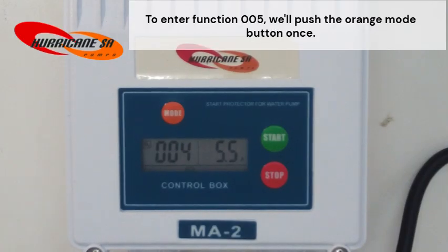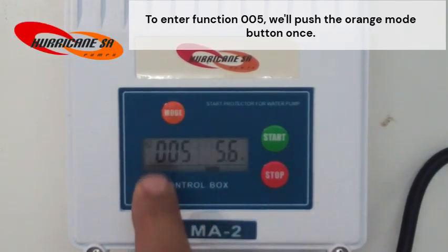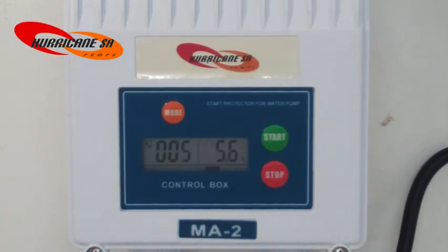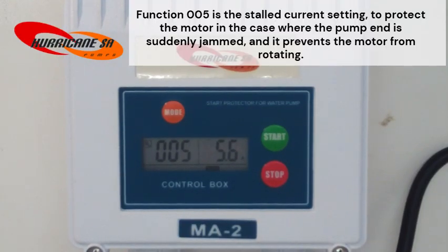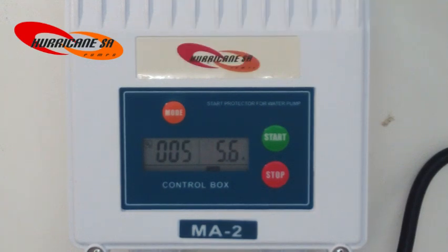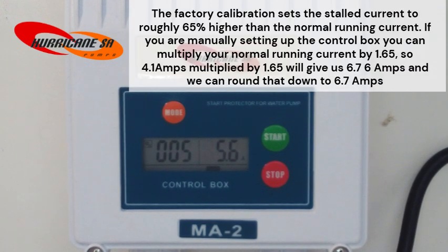To enter function 005, we'll push the orange mode button once. Function 005 is the stalled current setting to protect the motor in the case where the pump end is suddenly jammed, and it prevents the motor from rotating. The factory calibration sets the stalled current to roughly 65% higher than the normal running current.